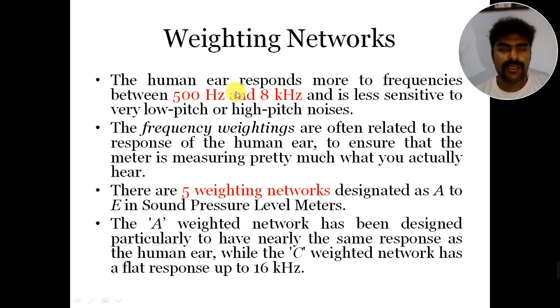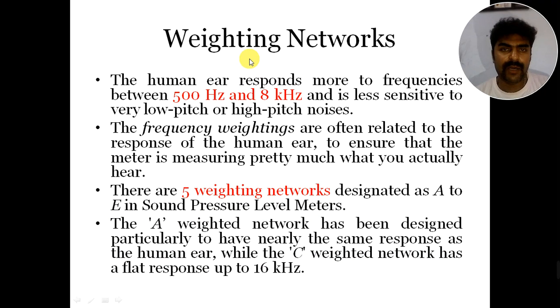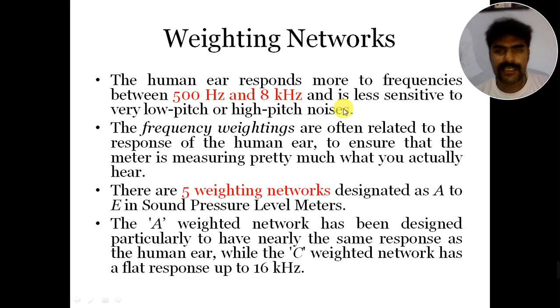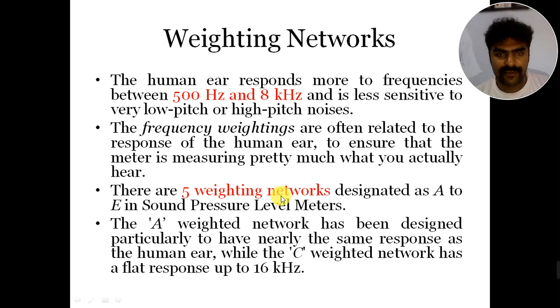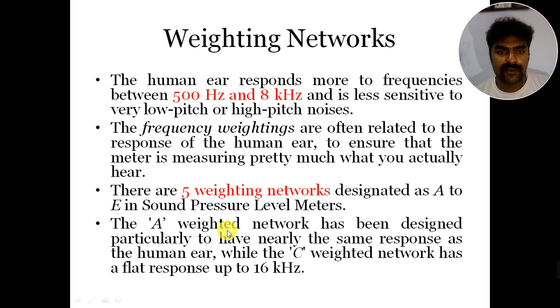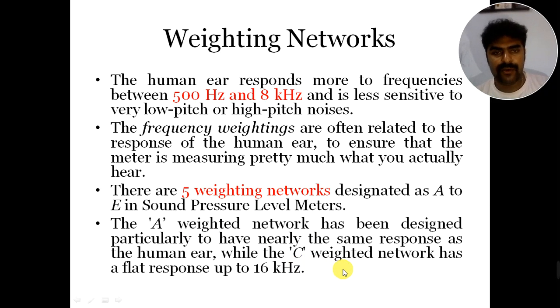The weighting network is another important part of the audible noise measurement circuit. A human ear responds most to frequencies between 500 Hz to 8 kHz, and is very less sensitive to very low pitch or very high pitch noise. In the circuit, there are five weighting networks designated as A through E in sound pressure level meters. The A network has been designed particularly to have nearly the same response as the human ear.